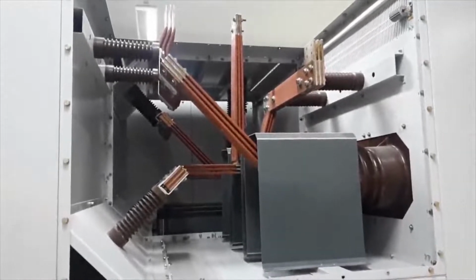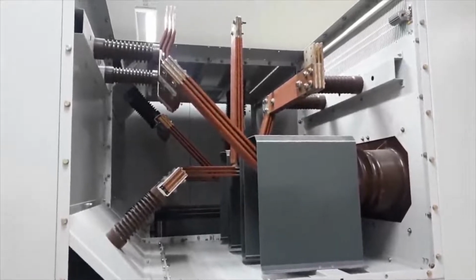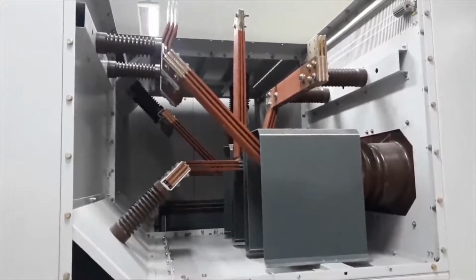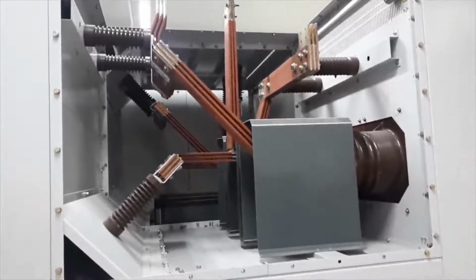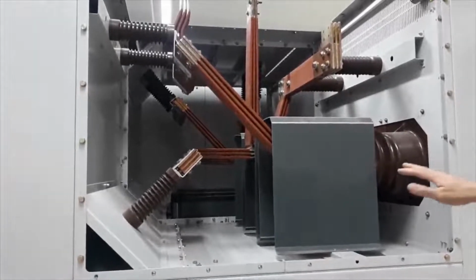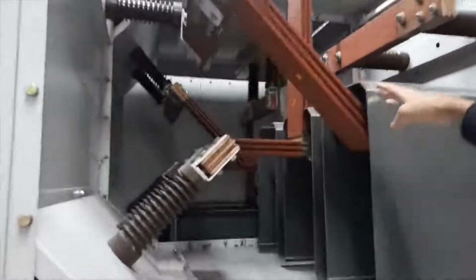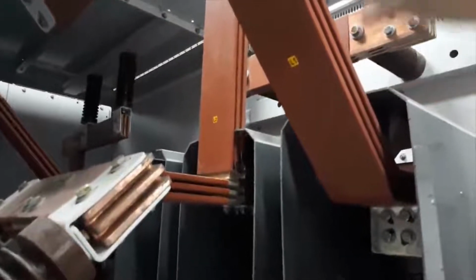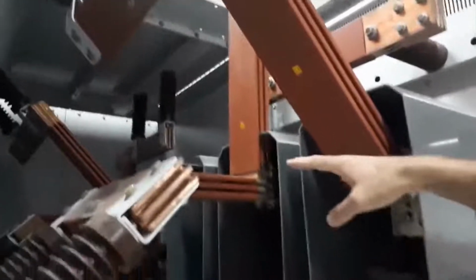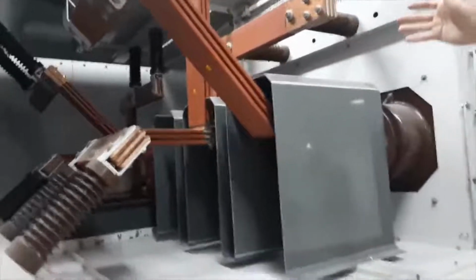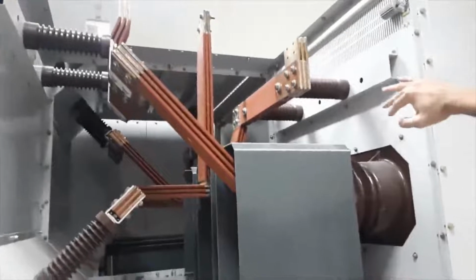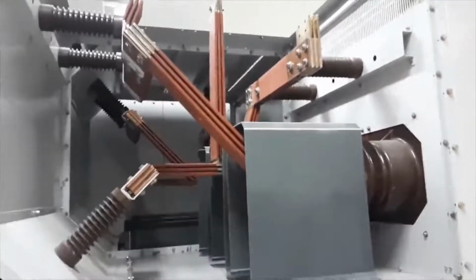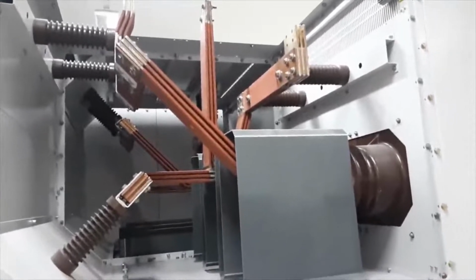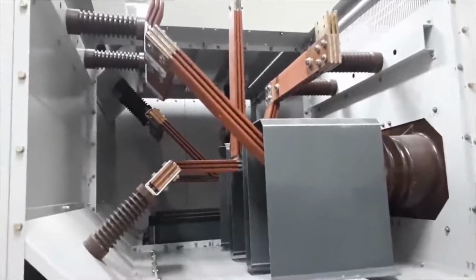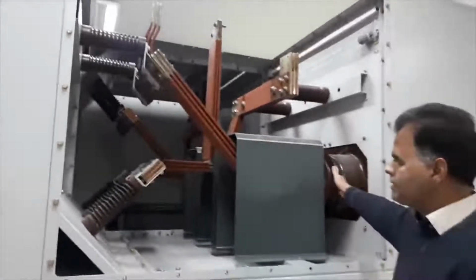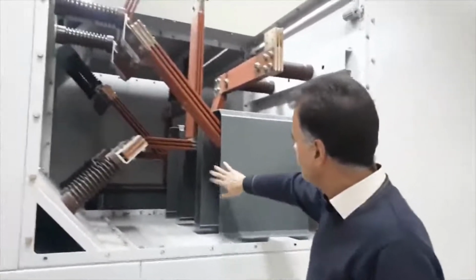Here you can see the 33 kilovolt switchgear bus bar. As you can see, the bus bar is arranged in a triangular shape to take up less space in the bus bar compartment. For example, phase R or L1 goes up, phase S or L2 goes down, and phase T or L3 goes diagonally, forming a triangular shape. And this bus bar arrangement reduces the volume of the bus bar housing, and it's the bushing that connects the breaker to the bus bar.